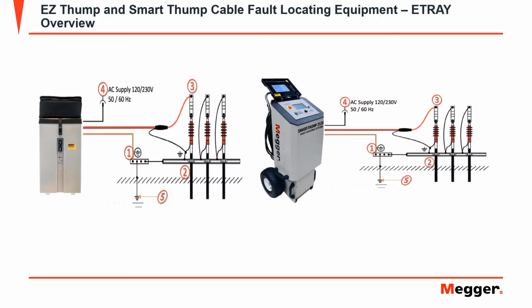For a brief connection overview, connect your ground lead to the system ground. Then connect your high voltage return lead to the concentric neutral or cable shield under test. Finally, connect your high voltage output lead to the cable under test.